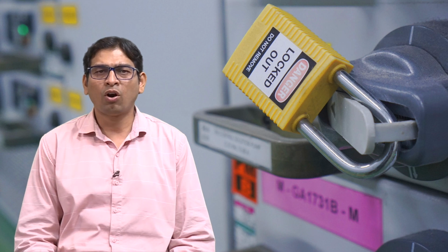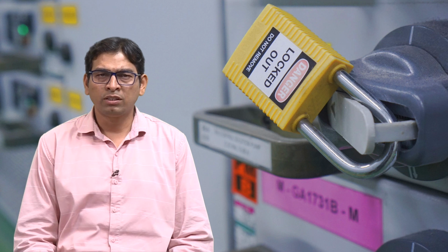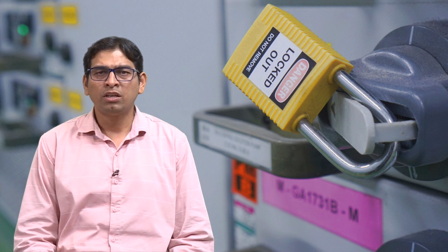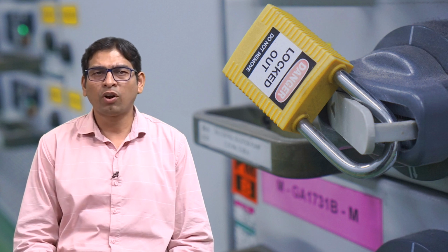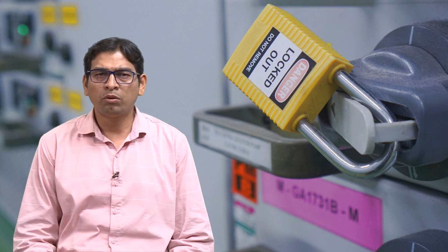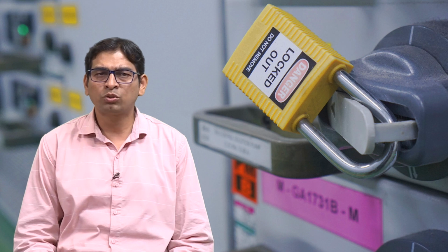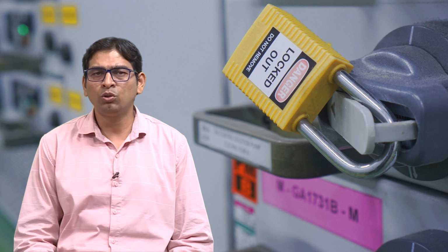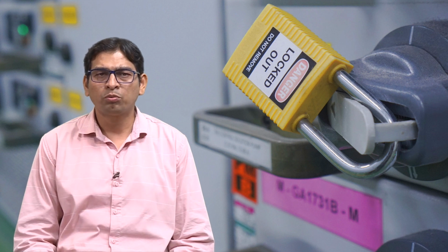Once you have performed all of your lockout tagout and energy dissipation procedures, you should test the machine to make sure that it will not operate. For electrical systems, you may first want to use a voltmeter to double check that no electricity is flowing. Next, press all the start buttons and throw all the switches and levers that would normally be used to activate the equipment. After you have determined that your lockout procedures are working, return all of the switches to their off position.